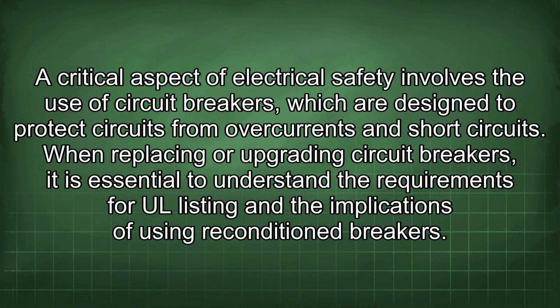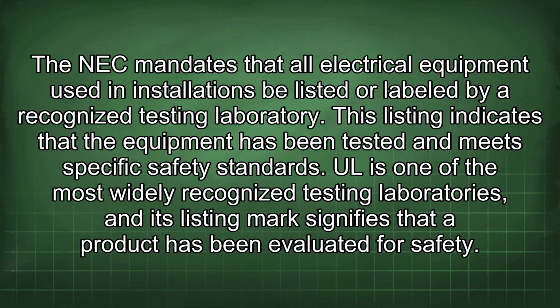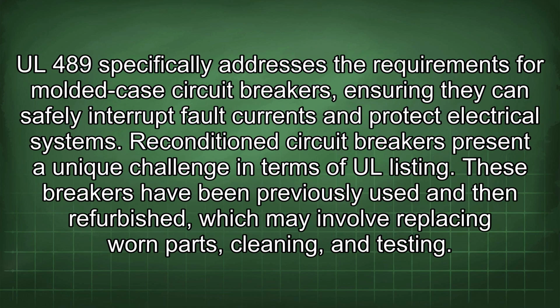When replacing or upgrading circuit breakers, it is essential to understand the requirements for UL listing and the implications of using reconditioned breakers. The NEC mandates that all electrical equipment used in installations be listed or labeled by a recognized testing laboratory. This listing indicates that the equipment has been tested and meets specific safety standards. UL is one of the most widely recognized testing laboratories, and its listing mark signifies that a product has been evaluated for safety. UL 489 specifically addresses the requirements for molded case circuit breakers, ensuring they can safely interrupt fault currents and protect electrical systems.